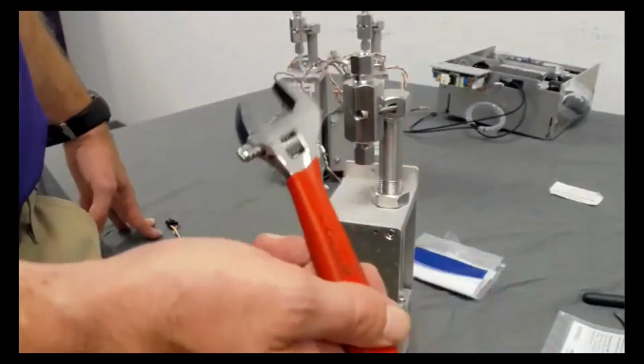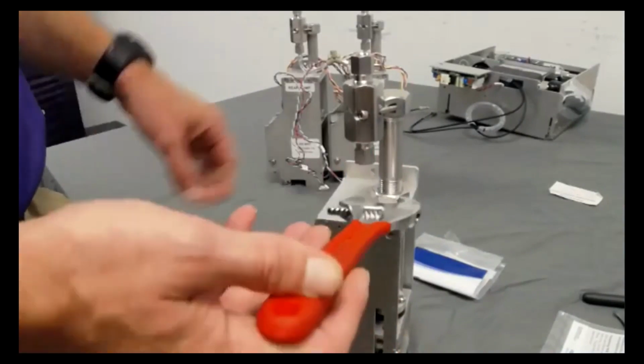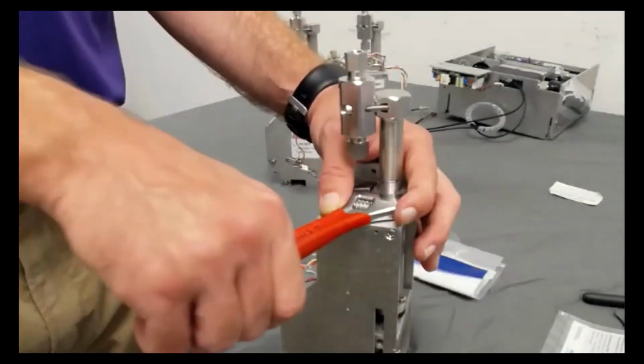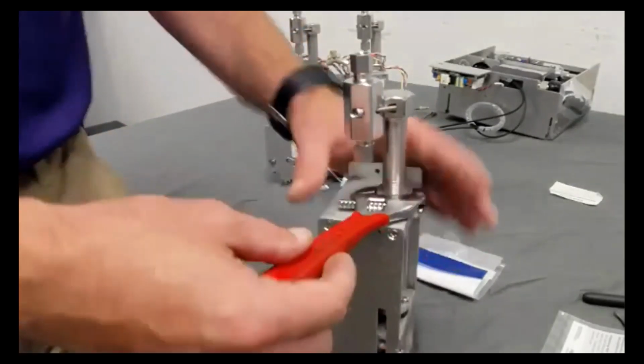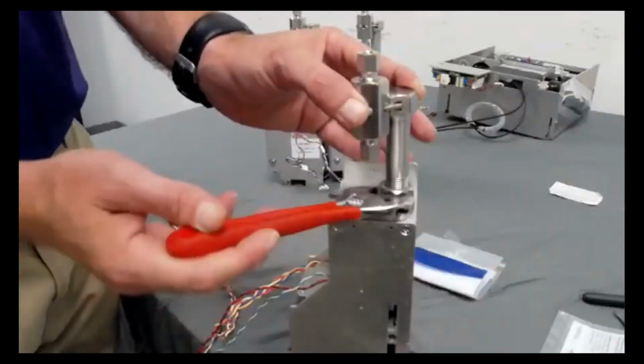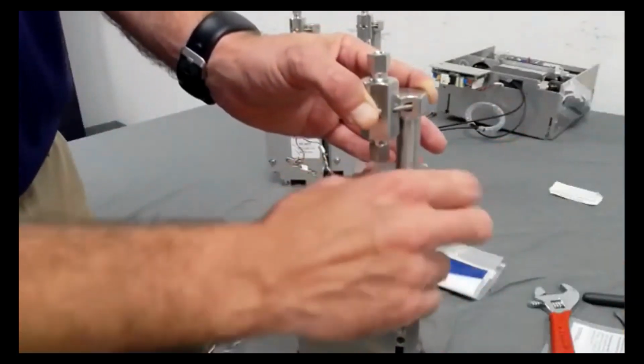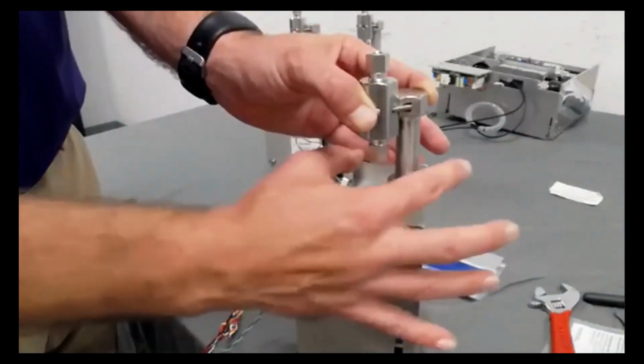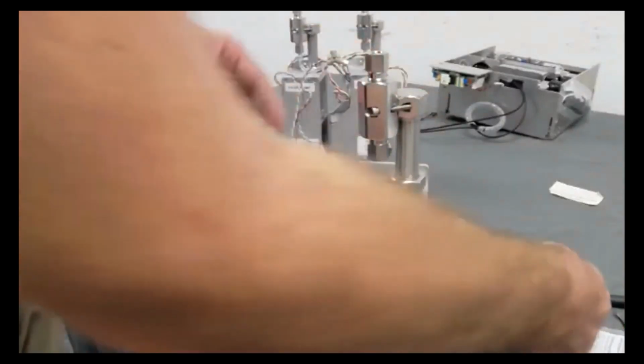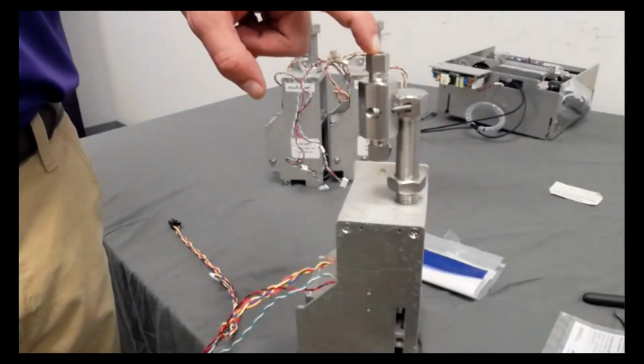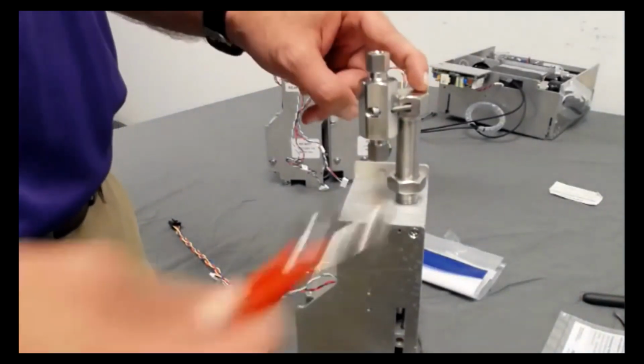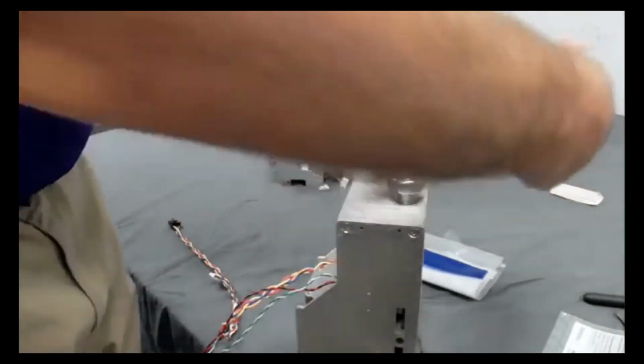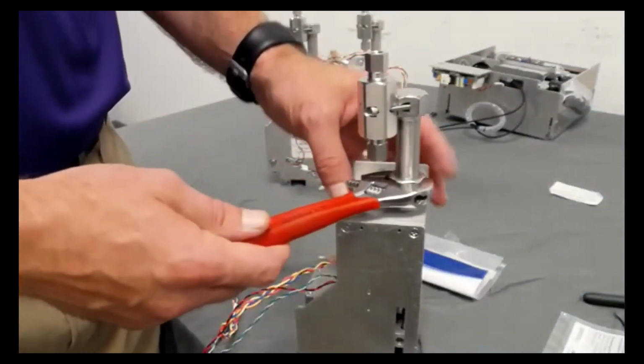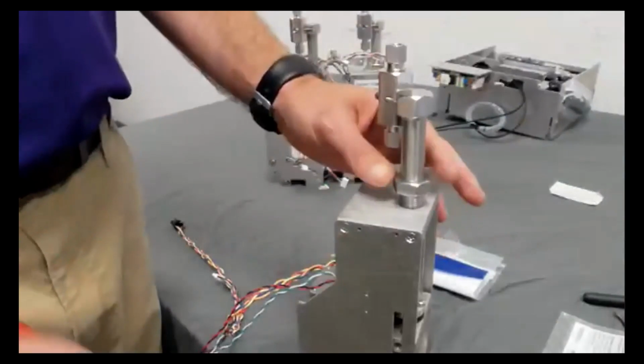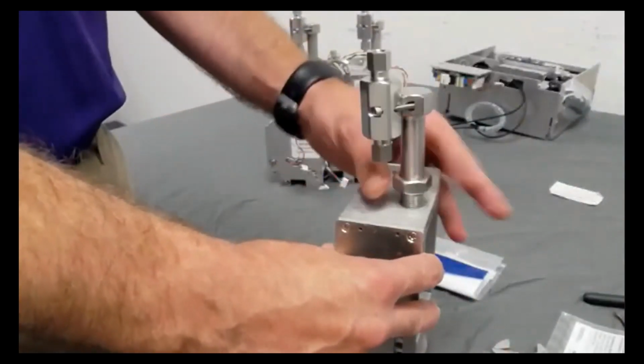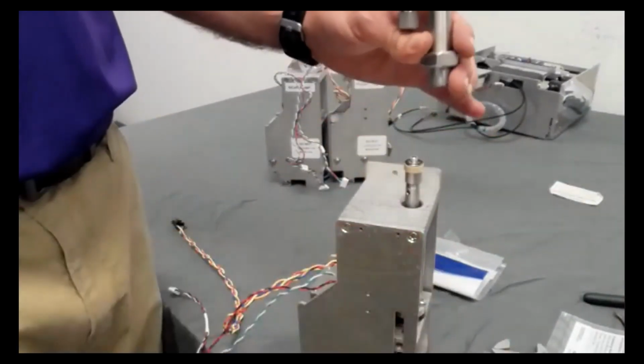Now, I'm not gonna lie to you, a lot of times you're gonna have to muscle this, all right? If you need to, you grab what's called a cheater bar, an extension bar you can put on here that gives you a little extra torque on your turn. If you get to the point where the jam nut can be threaded by hand, just thread it off all the way until it gets to the top of its threads. Now, you can do this with the check valve housing off or on, but if you want to remove the cylinder, you can use your wrench up here on the top of the cylinder. The reason I tell you to put the jam nut all the way up is it becomes our loosening point for the cylinder. So we're gonna loosen that cylinder all the way and it's gonna slide up and off, okay?